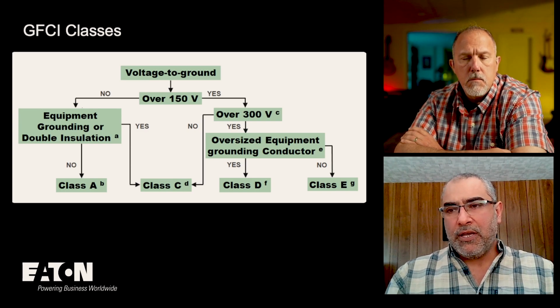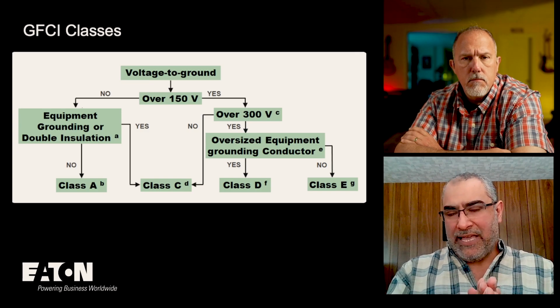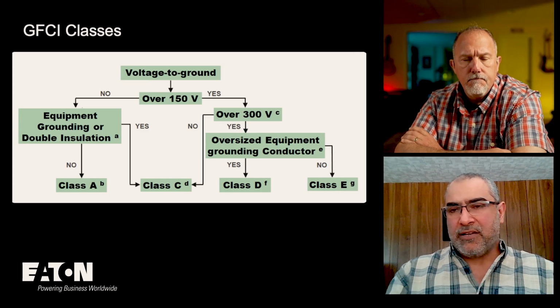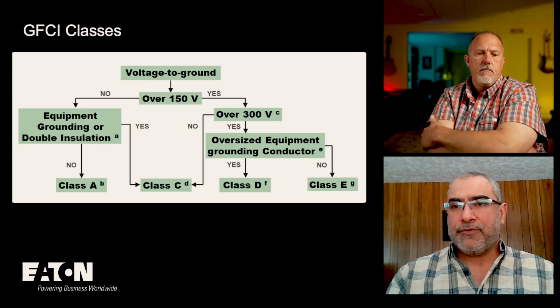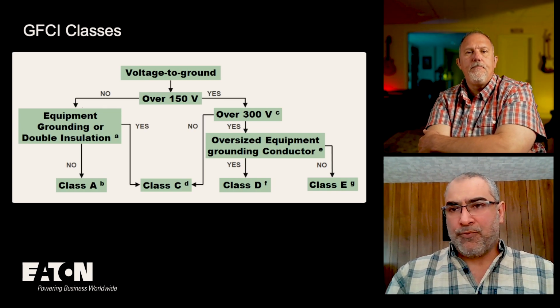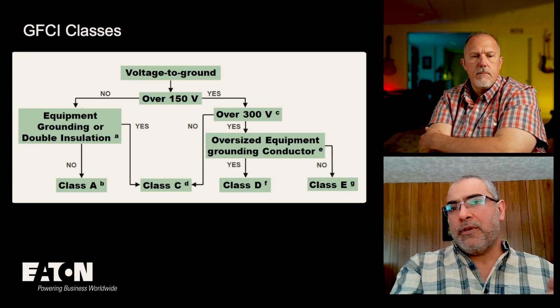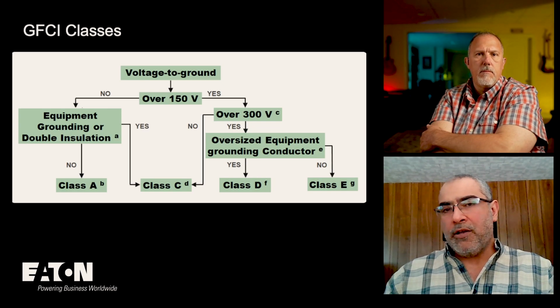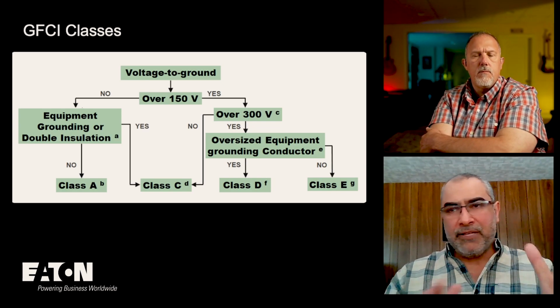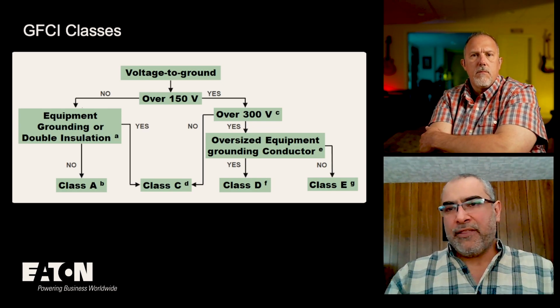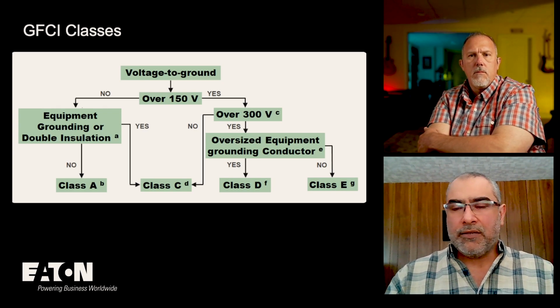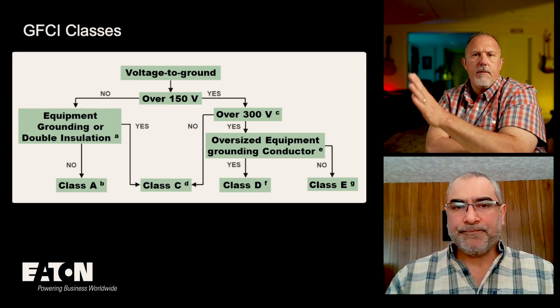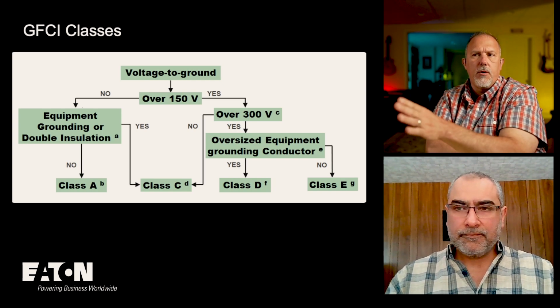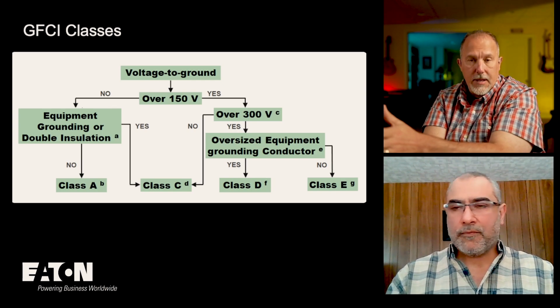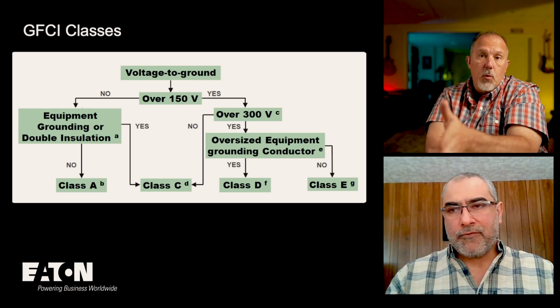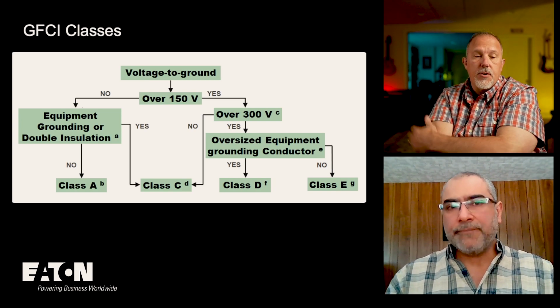So what they do is, we talk about Class A, 4 to 6 milliamp. These guys are 15 to 20 milliamp. So you are not supposed to trip at less than 15 milliamp. You must trip when it's 20 or higher. Between 15 and 20 milliamp, it's kind of a gray area, like the 4 to 6. And that's beyond the let-go threshold, but before the fibrillation threshold.